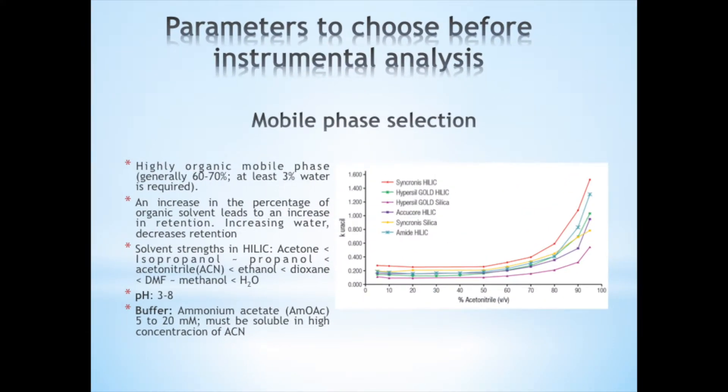Typical eluents for HILIC consists of 60 to 97 percent acetonitrile in water, or a volatile buffer. To obtain reproducible results, at least 3 percent water should be maintained in the mobile phase. This amount of water is necessary in order to ensure sufficient hydration of the stationary phase particles. Also, remember that a higher concentration of organic solvent in the mobile phase will increase the retention time.